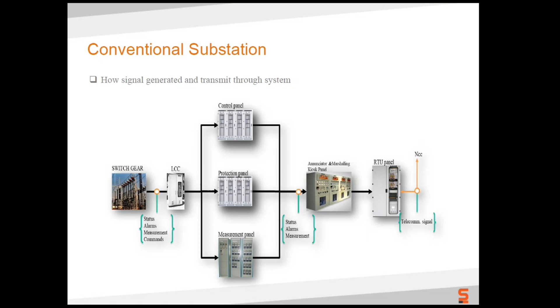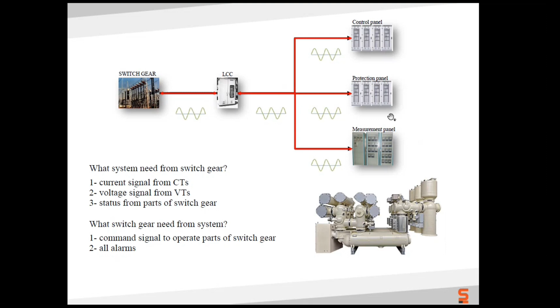As I said, what does the system need from switchgear? Current signal from CTs, voltage signal from VTs, status from parts of switchgear. And what does the switchgear need? Command signal to operate parts of switchgear, and alarms. You have to operate this breaker - the switchgear needs command from the LCC or NCC. So this is showing a conventional type of setup.